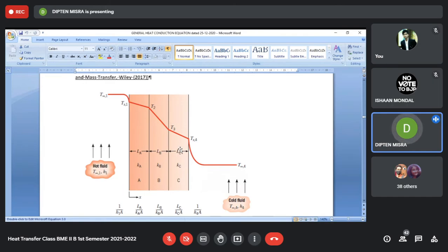So as far as the heat transfer rate is concerned, the order does not matter. But what will determine the order of placement of these layers is the safe working temperature of the respective material. This refractory has a very high working temperature. It can withstand a very high temperature. Insulation's working temperature may not be as high, and still lower will be the working temperature of the structural plates like a steel plate or a mild steel plate.